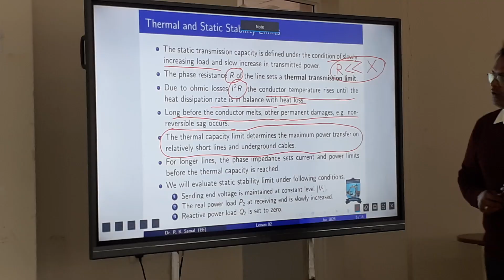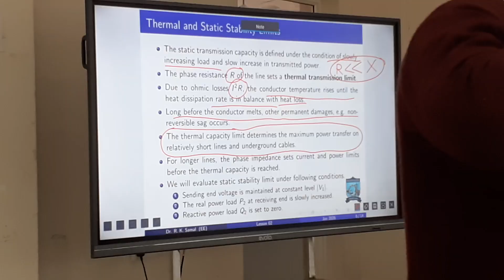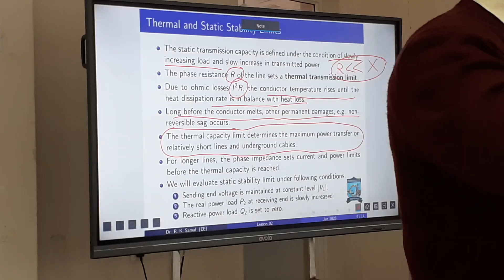Write it, thermal limit. Sir, will sag not occur in short lines? Yes, it will occur. Why do we not consider that? Because we don't reach the thermal limit. Okay. We say maybe 40%, 50% of the thermal limit we keep as a design limit. Now we are not bothered about that in longer lines because the stability limit will reach first. But in case of a shorter line, the stability limit and thermal limit may be near to each other. Okay.